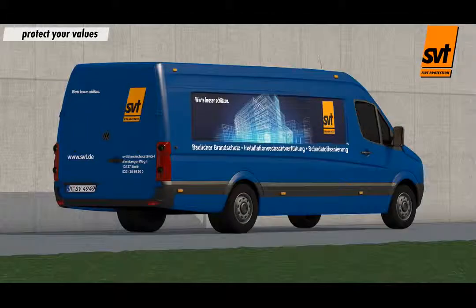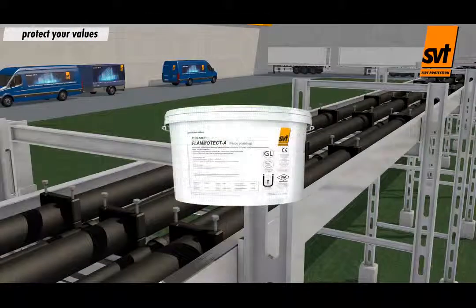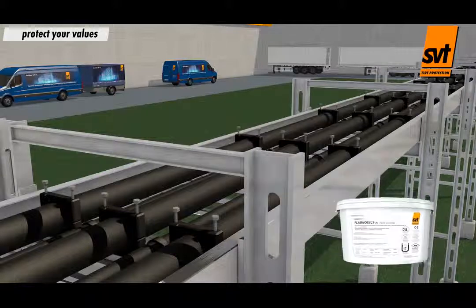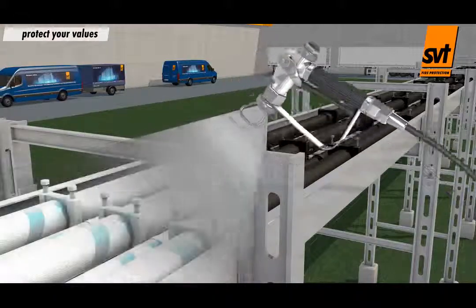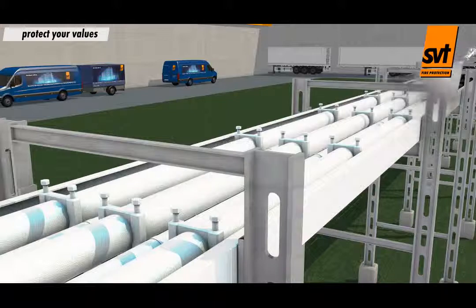PyroSafe Flammotect A can be used for indoor and outdoor cable systems. The product is available in three viscosities to suit your application needs. With the application of PyroSafe Flammotect A coating, GL-certified dry film thicknesses of 0.5 mm in accordance with IEC 60332-3 can typically be achieved in a single step.